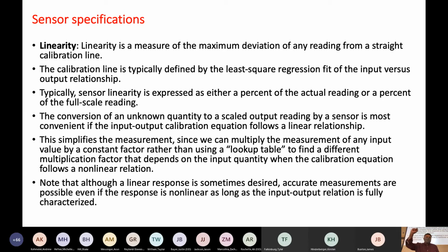And as you can see, it could be a straight line, but eventually it might actually curve off. That's a very typical behavior with a lot of different types of sensors, where you do not have this straight line relationship. So many times we would refer to linearity as a percentage, and we would say that this sensor has 90% linearity, which means that for 90% it's linear, after that it's not going to be linear. It's important to know that linearity is not so much of an issue these days because we have better computer programs to actually model that behavior. And so we can fit the algorithm into the electronics, so we know that beyond this concentration it's not linear, so it can read the values much more accurately.